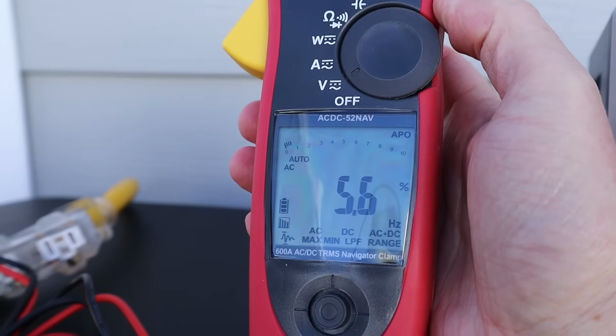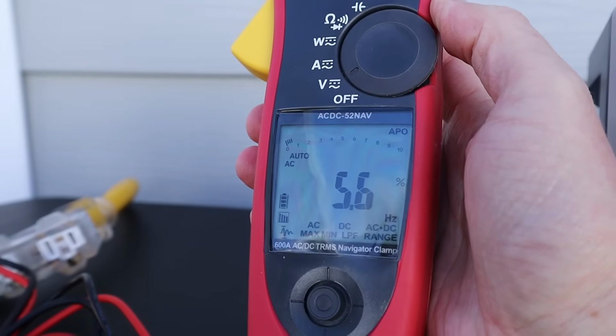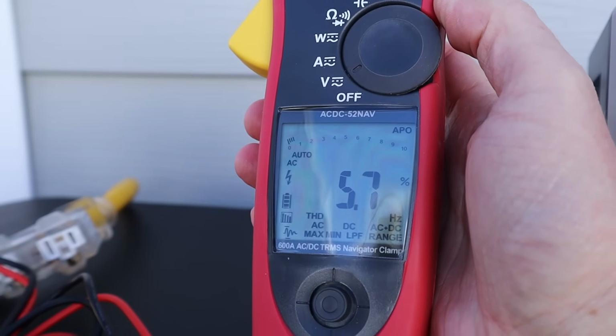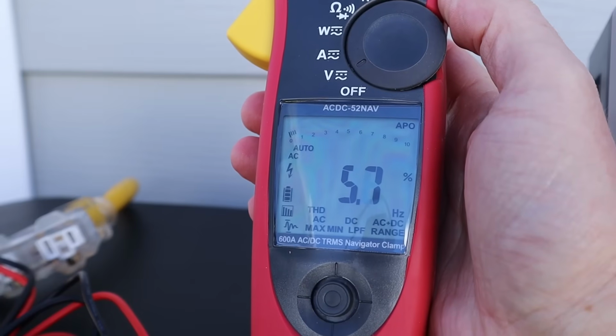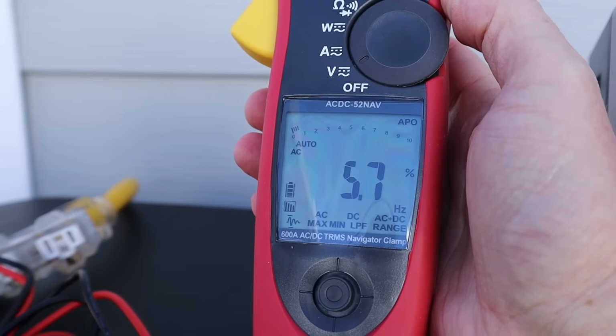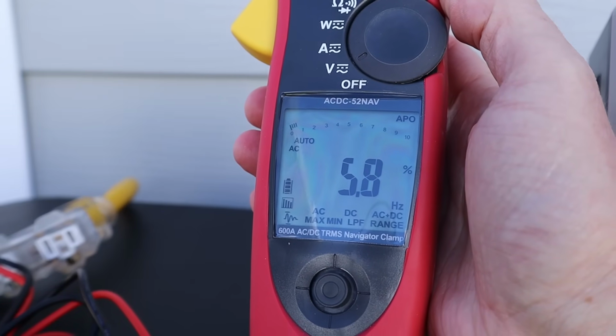In this test, I've connected up my amp probe meter to measure total harmonic distortion. Typically you want to see under 3%, and we're sitting at about 5.8%, so quite a bit off from what you'd like to see from the power output.